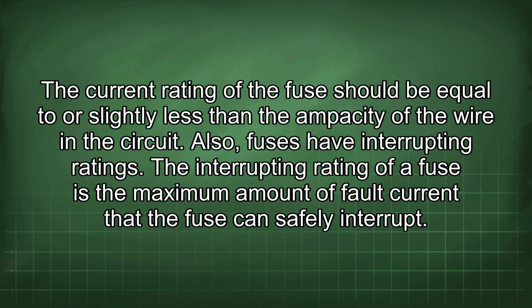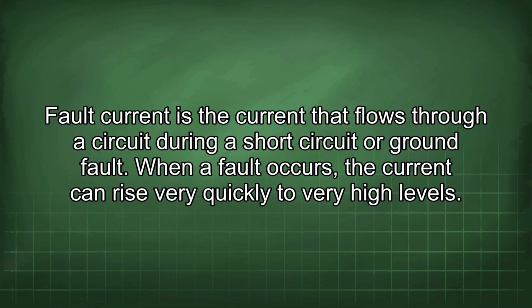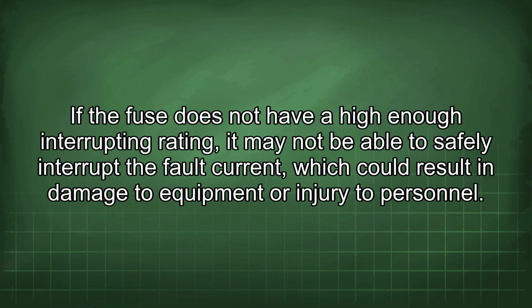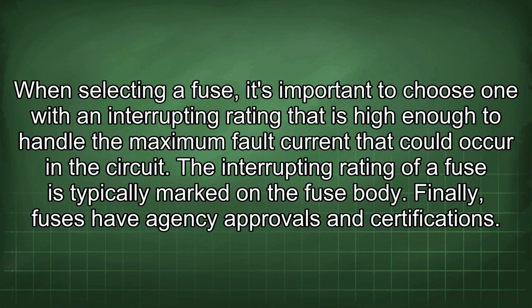Also, fuses have interrupting ratings. The interrupting rating of a fuse is the maximum amount of fault current that the fuse can safely interrupt. Fault current is the current that flows through a circuit during a short circuit or ground fault. When a fault occurs, the current can rise very quickly to very high levels. If the fuse does not have a high enough interrupting rating, it may not be able to safely interrupt the fault current, which could result in damage to equipment or injury to personnel. When selecting a fuse, it's important to choose one with an interrupting rating that is high enough to handle the maximum fault current that could occur in the circuit.